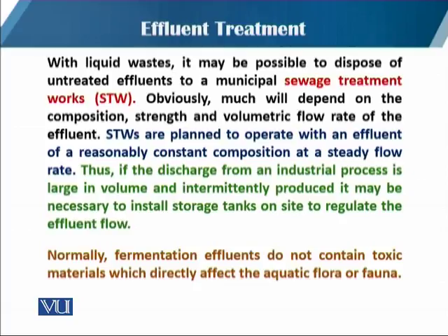The sewage treatment works are planned to operate with an effluent of reasonably constant composition and steady flow rate. Thus, if the discharge from an industrial process is large in volume and intermittently produced, it may be necessary to install a storage tank on the site to regulate the discharge of the effluent into that system. Normally, fermentation effluent does not contain toxic material which may directly affect the aquatic flora and fauna of the water courses.